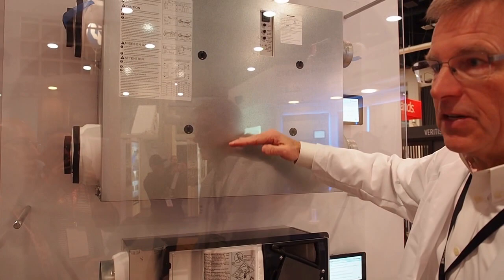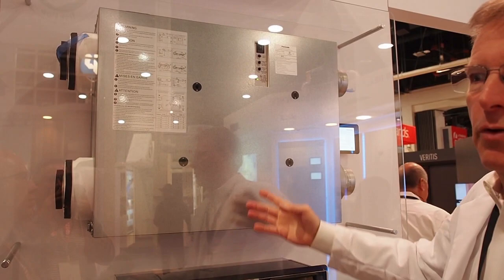The IntelliBalance I have 10, 20, 30, 40. IntelliBalance will go 50, 60, 70, 80, 90, and 100. So again 3,000 square feet is going to require about 90 CFM continuous. I can do that with the IntelliBalance pretty easily.